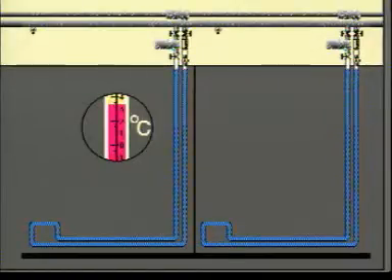Note that fresh water expands when the temperature begins to fall below 4 degrees centigrade. At 0 degrees centigrade, it turns to ice. If ice blocks the expanding water, the coil will break.